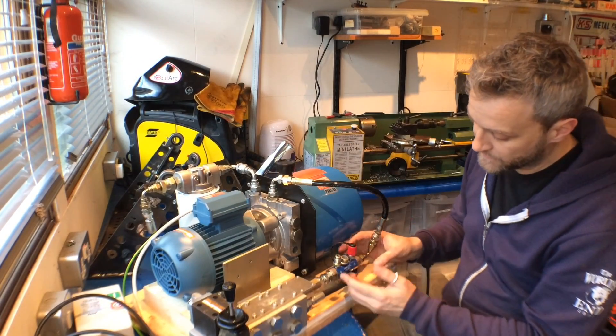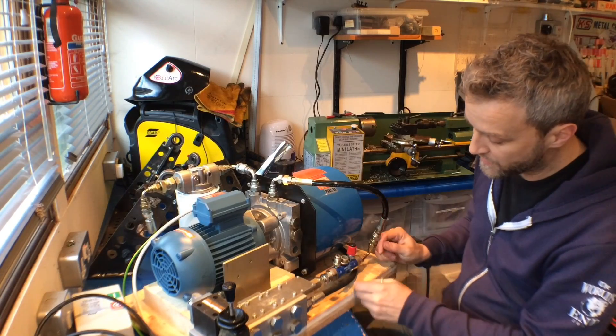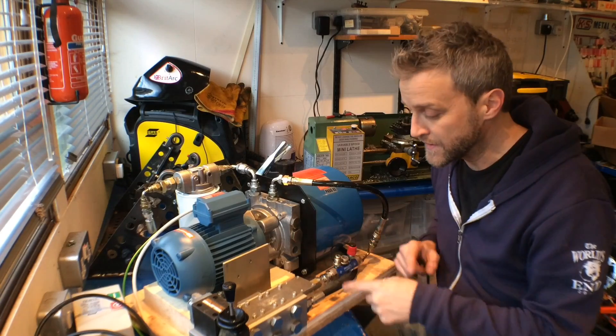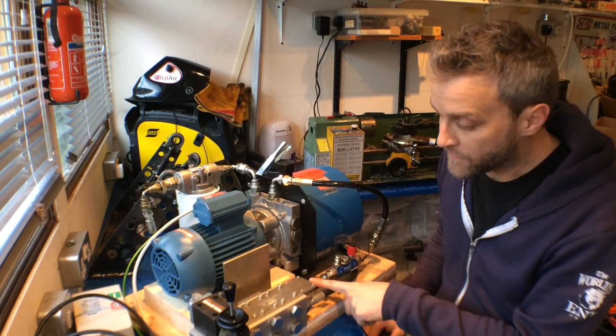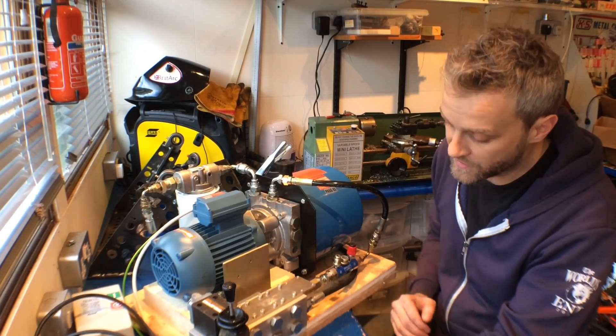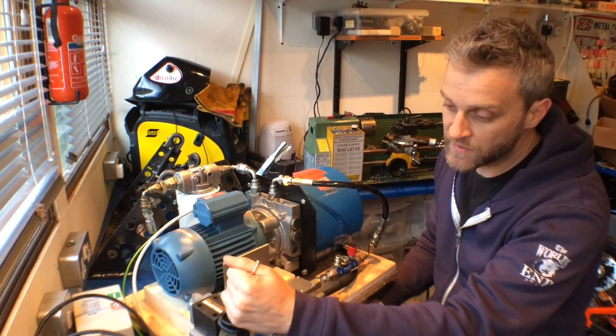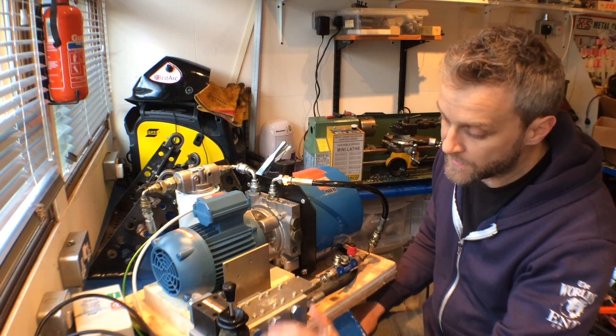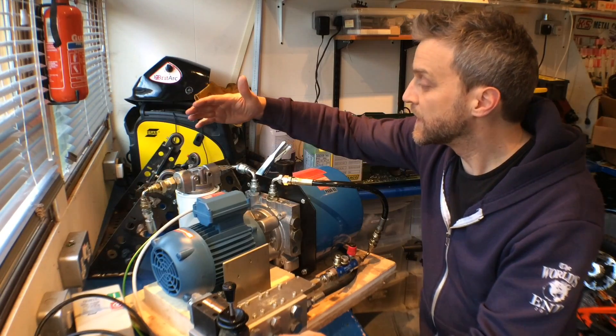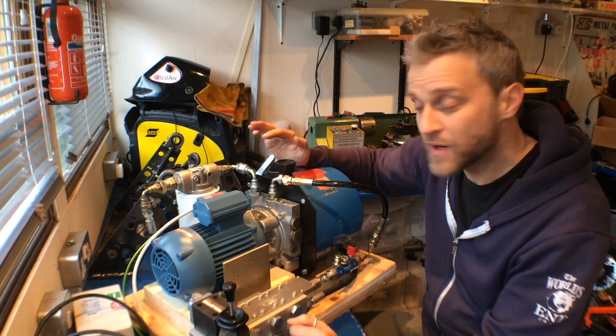Coming down here, this is the little hydraulic multimeter test point - I can plug in here to measure pressure, temperature and flow. Then there's a check valve going into the C.E.T.O.P. manifold. It's a four station manifold as mentioned, and I've only got one station in use at the moment - this manual lever control valve. The rest are blanked off. Then the return line comes back to the filter, through the filter and back into the tank.